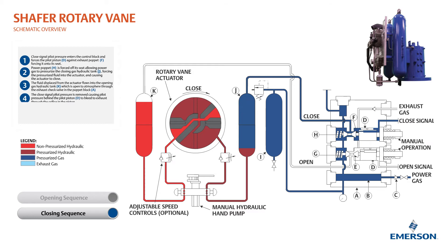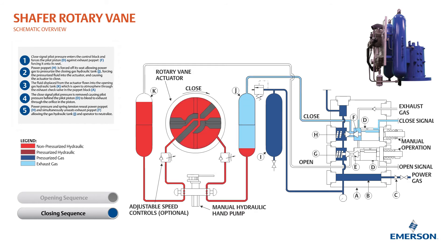The closed signal pilot pressure is removed, causing pilot pressure behind the pilot piston to bleed to exhaust through the orifice in the piston. Power pressure and spring tension reseat the power poppet and simultaneously unseat the exhaust poppet, allowing the gas hydraulic tank and operator to neutralize.